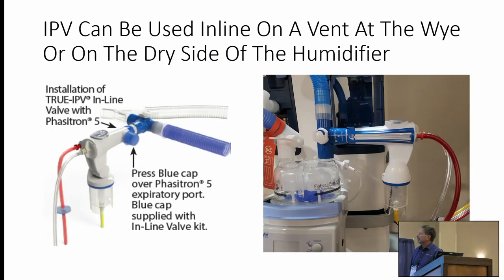IPV can be used in line on a vent at the Y, or on the dry side if it's a neonatal size circuit, since those are smaller and don't have a 15/22 connection at the Y. So we recommend it here for neonatal, but you can also do pediatrics and adults that way. If you put it before the dry-side humidifier, you don't have to put anything in here because it's picking up all the humidity from the humidifier.